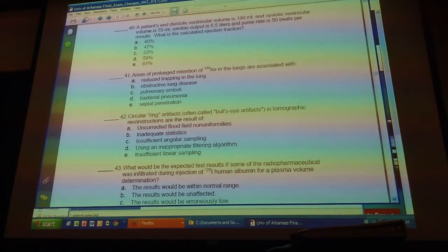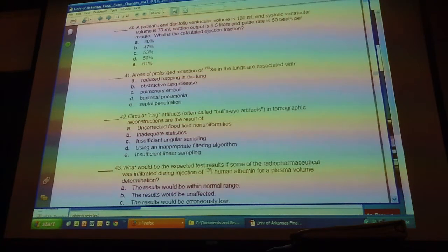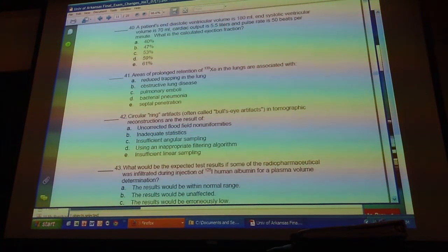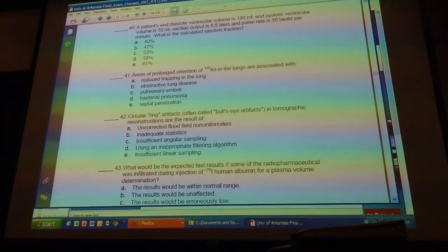That's the reason why you have to do those. When you do uniformity correction, there are actually two aspects. One, you take a picture to show that it is uniform. Then you also have what they call a uniformity correction program, which requires a new flood or new set of numbers to correct.